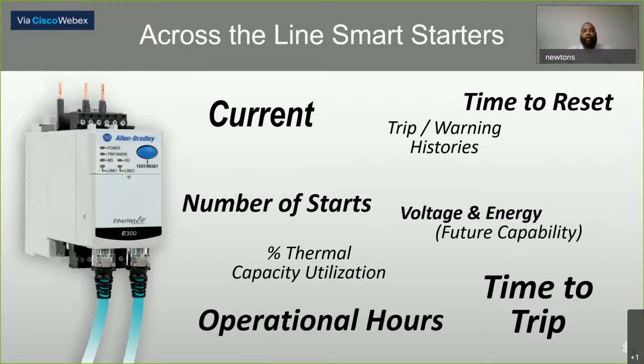When we use an across the line smart starter, if you had a process or application or a motor where, as soon as you hit the go button, as soon as you initiate a start, you want it to ramp up to full speed as quickly as possible, the across the line starter will be the solution for that. It's going to be the lowest cost between the 3 different solutions, and probably one of the simpler ones to troubleshoot.